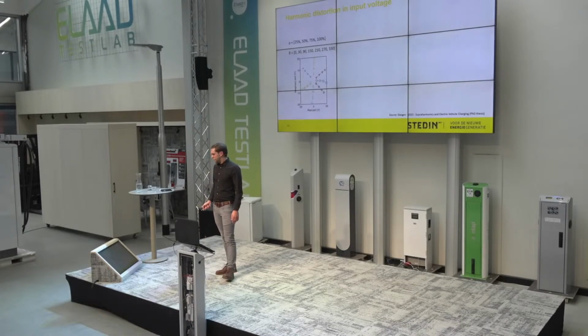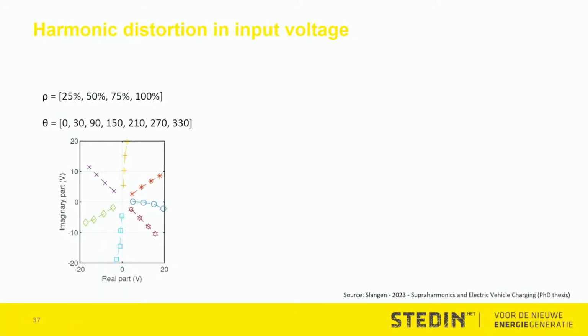In this example, we have what we call a complex diagram of a harmonic voltage. A harmonic might occur at a certain amplitude, a few amounts of a volt, and a certain phase angle, anything from in phase with the fundamental to totally out of phase, and any random value in between. Using a source that can inject harmonics at different amplitudes and angles, you can get an idea of how the device will react in certain grid environments.